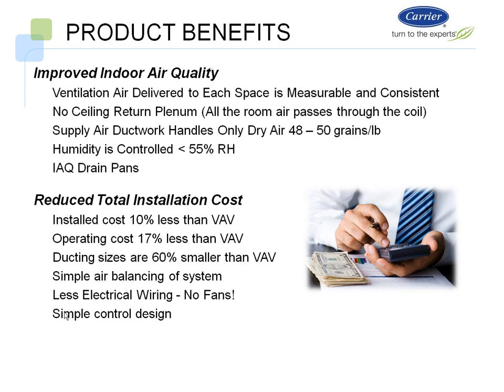Typical installation costs that we've seen is our overall installed cost about 10% less than a VAV system. Operating costs, again, are 17% less than a VAV, and that's being very, very conservative. I think it can be even more than that depending on the size of the building, if you're introducing fan coil units as well as VAV boxes and how many there are. Again, the air balancing becomes much simpler, so that part of your project cost gets less. And there's a lot less electrical wiring because there are no fans now in the space. So the only electrical wiring that's going inside the actual spaces is to your lighting and not to these, except for the low voltage of a control valve that opens and closes for the unit.